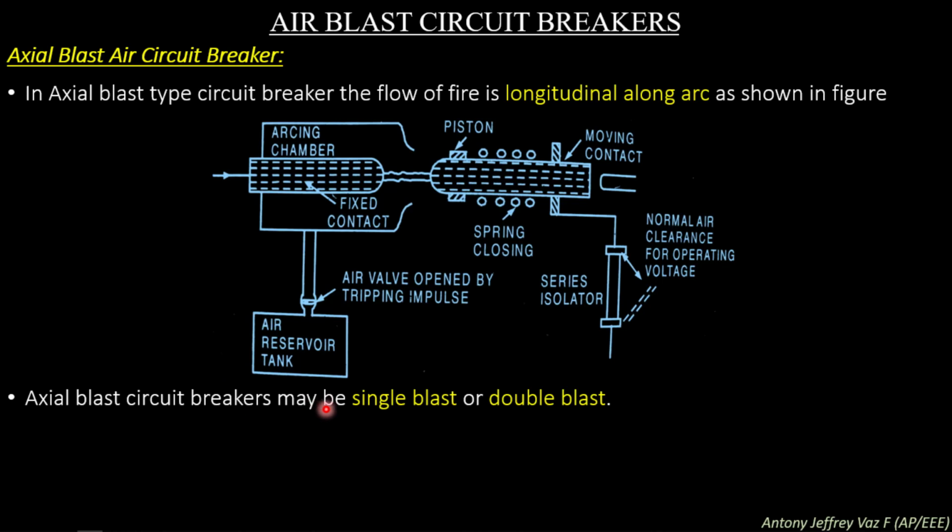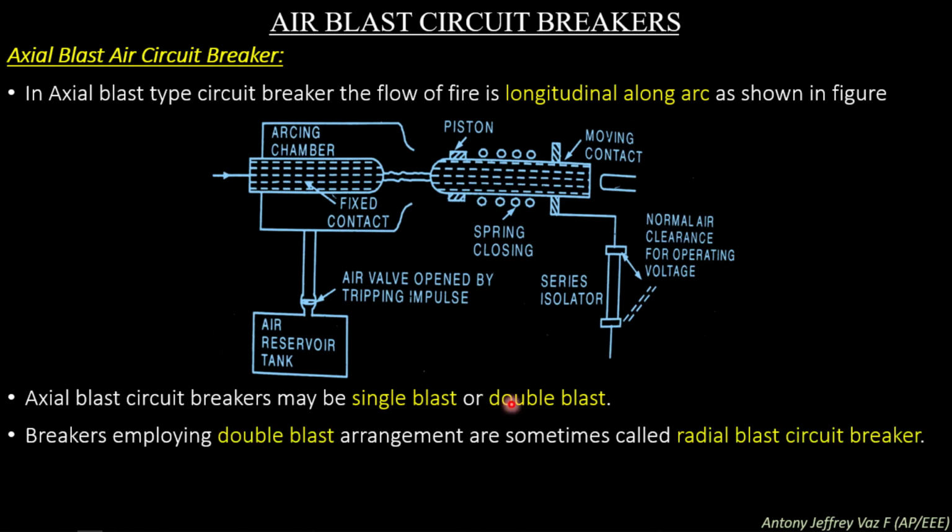Axial blast circuit breakers may be of single blast or double blast. If a single reservoir tank and a single air valve is opened, then it is known as single blast. If double reservoir tank with double air valve is opened, then it is known as double blast. Breakers employing double blast arrangements are sometimes called radial blast circuit breakers.